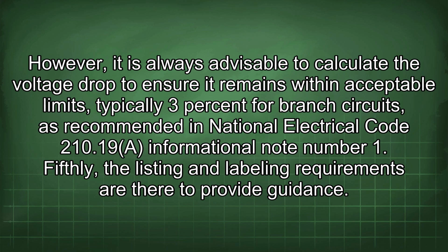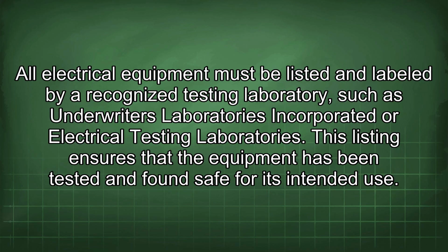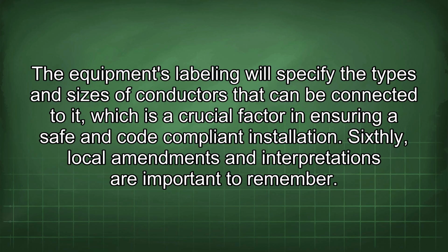Fifthly, the listing and labeling requirements are there to provide guidance. All electrical equipment must be listed and labeled by a recognized testing laboratory, such as Underwriters Laboratories Incorporated or Electrical Testing Laboratories. This listing ensures that the equipment has been tested and found safe for its intended use. The equipment's labeling will specify the types and sizes of conductors that can be connected to it, which is a crucial factor in ensuring a safe and code-compliant installation.